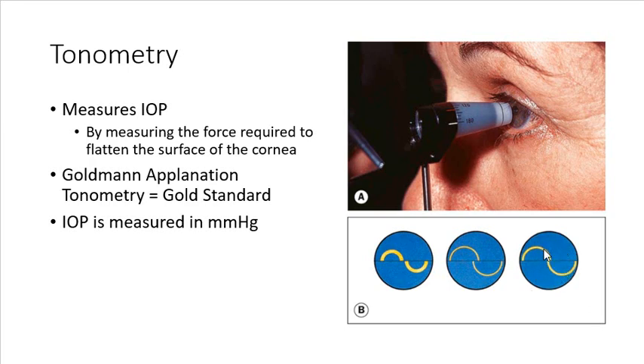So once you've aligned the position, so you align the inner margins, you read the dial of the intraocular pressure reading off the tonometer itself. So this one here shows that it's out of alignment, it's too far inwards, and this one here is too far outwards. So this one on the right-hand side is just perfect. And the pressure reading that it gives you is in millimeters of mercury.